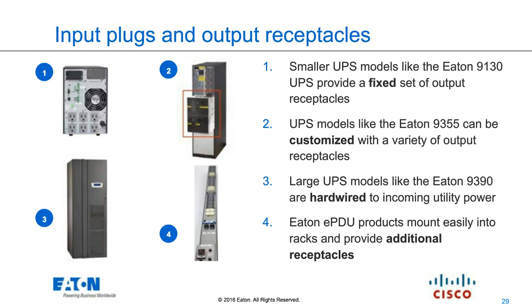Most IT equipment can get through that 4 milliseconds without even knowing anything has happened. If there's ever any concern, if it's a really high-end server that tends to put out more harmonics than an average server, that's when we'd push you toward our 9130 product line, or bigger depending on the size of the server, maybe even a 9PX, which gets you up to the 5 or 6 kVA mark.